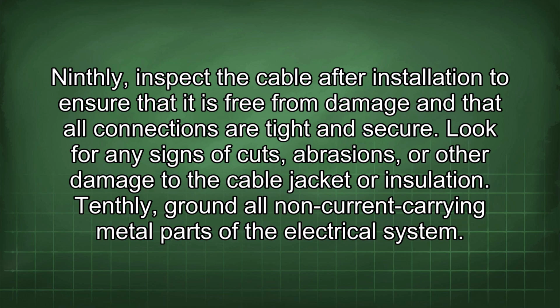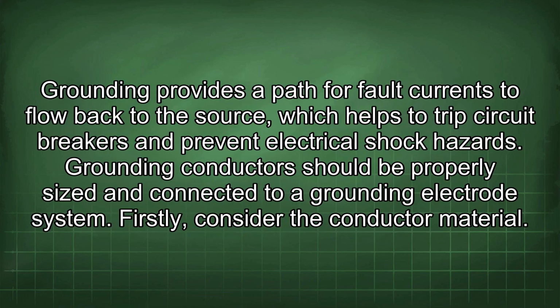Tenthly, ground all non-current carrying metal parts of the electrical system. Grounding provides a path for fault currents to flow back to the source, which helps to trip circuit breakers and prevent electrical shock hazards. Grounding conductors should be properly sized and connected to a grounding electrode system.